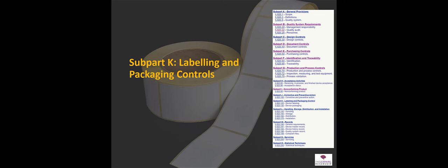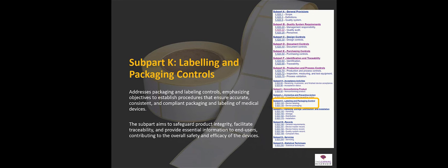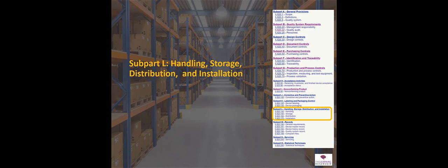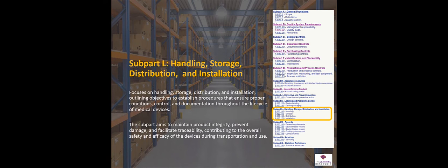Sub-part K outlines the requirements for labeling and packaging controls — we want to have our devices labeled and packaged correctly, and those requirements are covered under sub-part K. Sub-part L covers handling, storage, distribution, and installation of your devices. You want your devices handled correctly, stored correctly, sent out to patients or hospitals correctly, and installed correctly. It's critical that these important parts of the medical device life cycle are controlled, and the requirements for that are found in sub-part L.